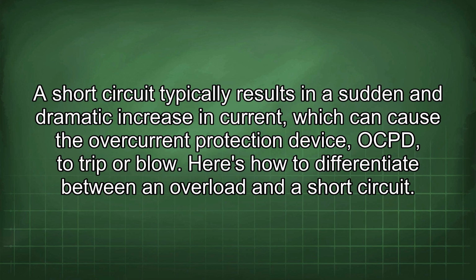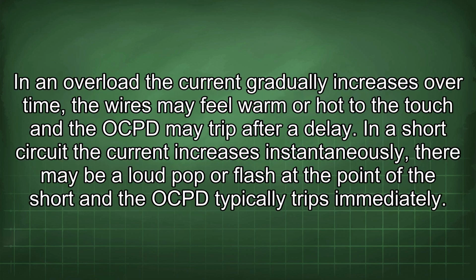Here's how to differentiate between an overload and a short circuit. In an overload, the current gradually increases over time. The wires may feel warm or hot to the touch, and the OCPD may trip after a delay. In a short circuit, the current increases instantaneously. There may be a loud pop or flash at the point of the short, and the OCPD typically trips immediately.